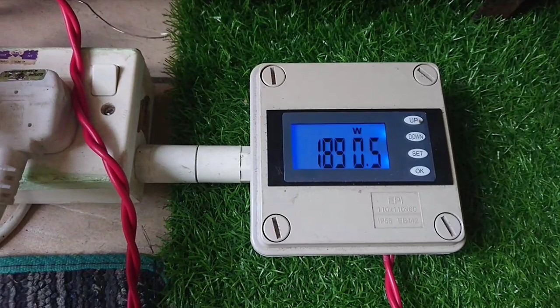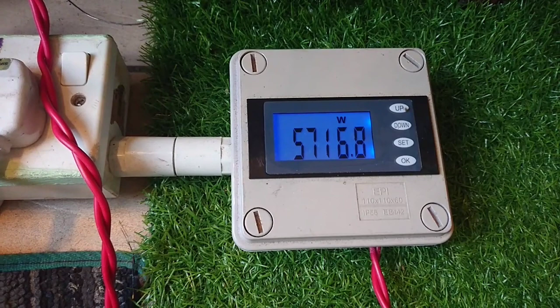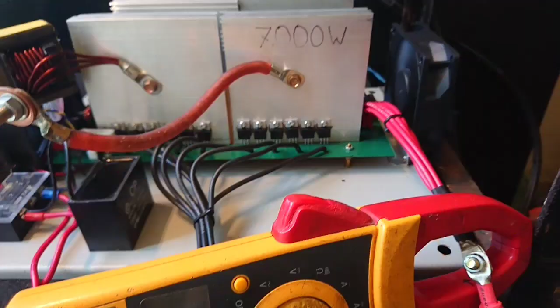Okay, 7 kilowatt, go. 2 kilowatt, 3 kilowatt, 6 kilowatt, 7 kilowatt. It's a bingo, 7 kilowatts. The voltage is maintained at 224. The current is 150 amps. And then take the temperature of the pads. It's normal, not heating anymore. The fan is running at full speed. 40 Celsius, it's normal. This is the grid pads, 43, fan at full run.